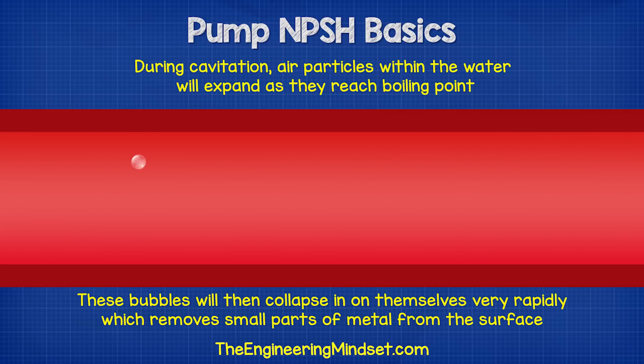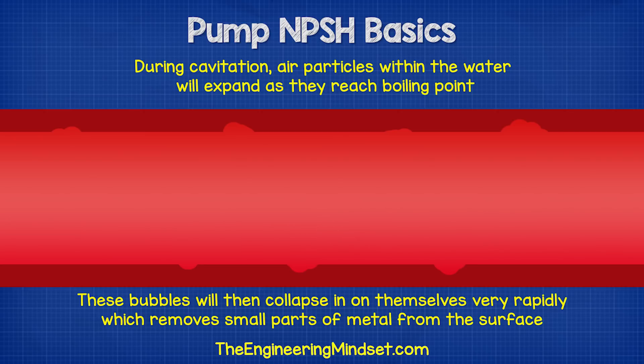During cavitation, air particles within the water expand as they reach boiling point. These will then collapse in on themselves very rapidly. As they collapse, they will damage the impeller as well as the pump casing. This removes small parts of metal from the surface, and if this keeps occurring, it will eventually destroy the pump. Therefore, we must ensure the available pressure is higher than the required pressure of the pump.